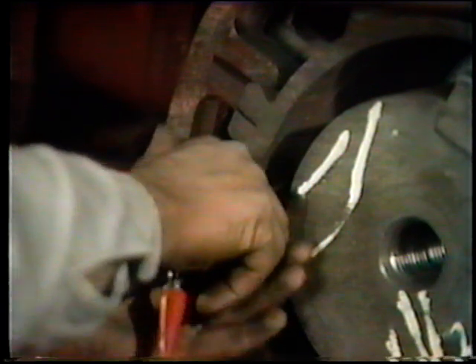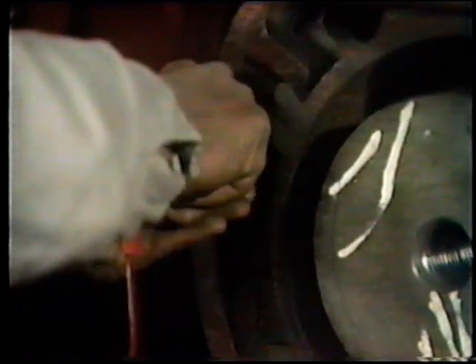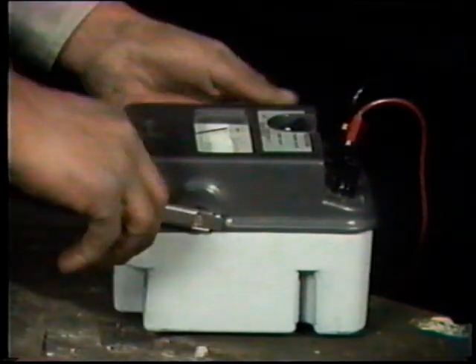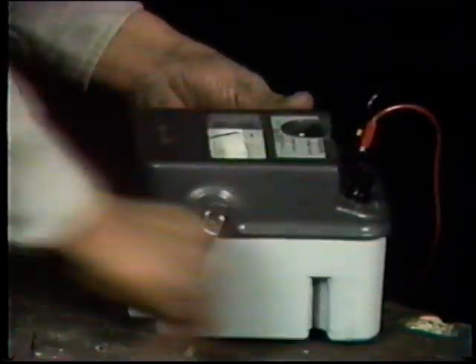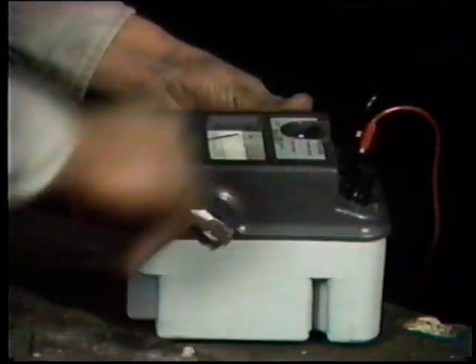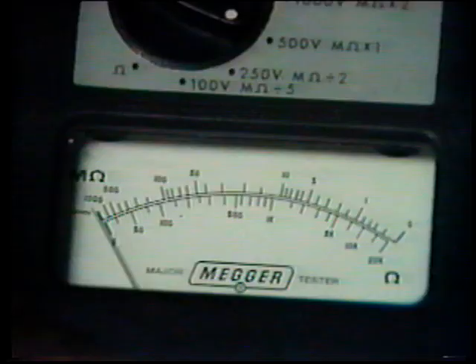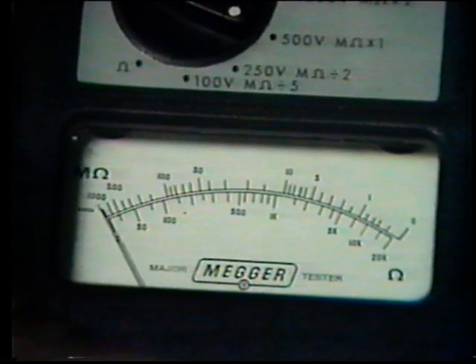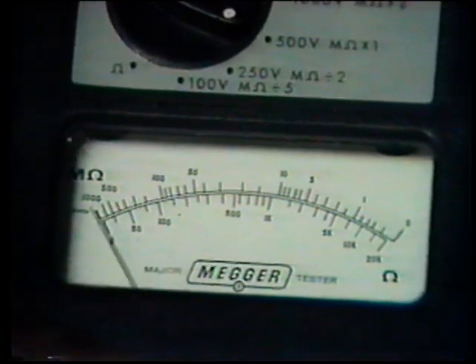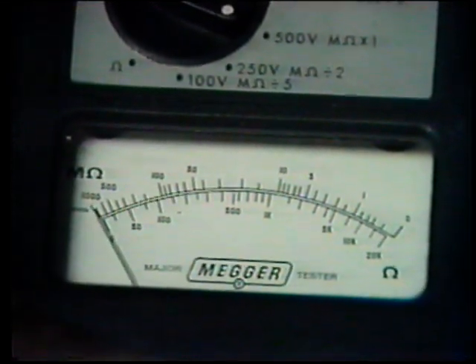Now attach the line lead to one of the slip rings. The meg-ohm meter is operated for 1 minute. As a rule of thumb, a reading of at least 1 megohm for each 1,000 rated volts with a minimum of 1 megohm should be indicated on the meg-ohm meter. If it isn't, there may be a problem with the insulation. The reading here is infinite resistance. This indicates that the insulation is in pretty good shape.